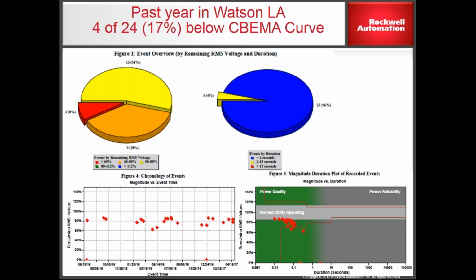The other thing I see here are a couple of lines working through the graph, from the bottom up to the right, or from the top down to the right. Those represent the ITIC CBEMA curve, a North American standard for electronics design impact voltage. So we expect voltage to be in the zone between those 2 lines, and when we design that piece of electronics, that's what we design it to.